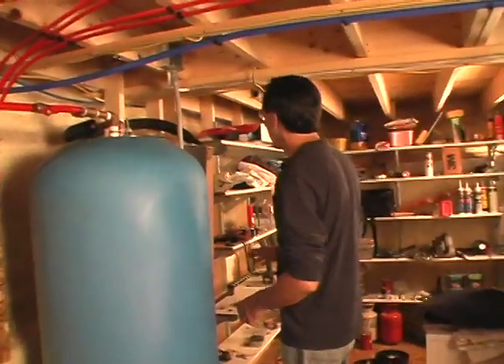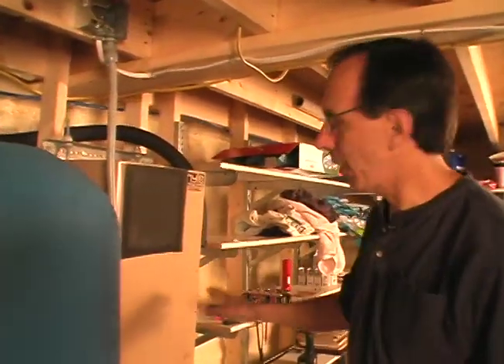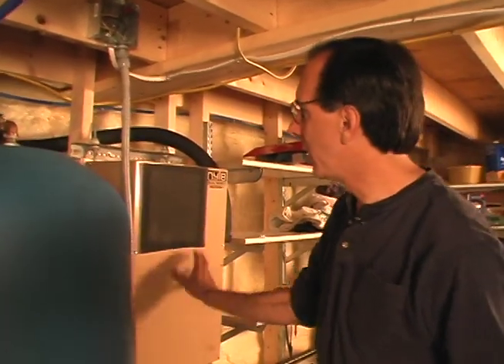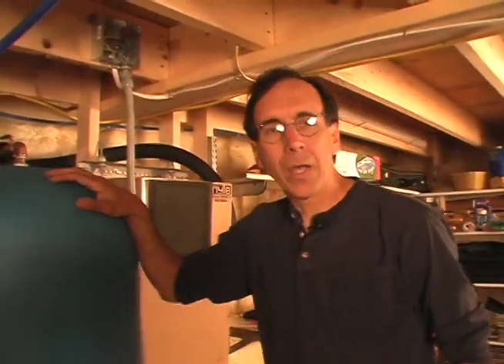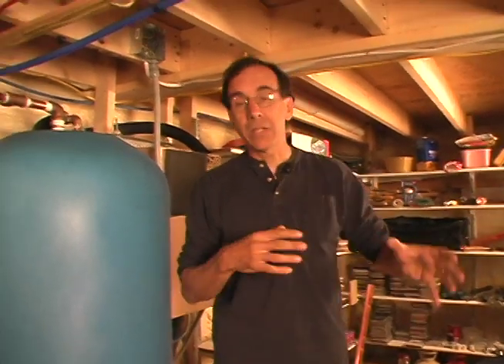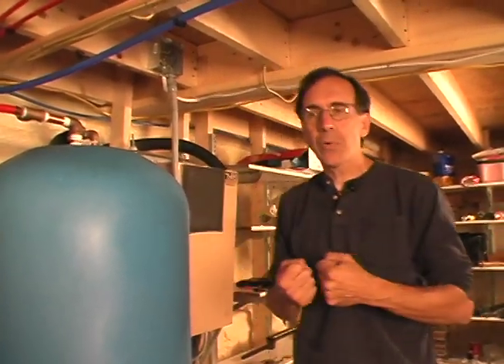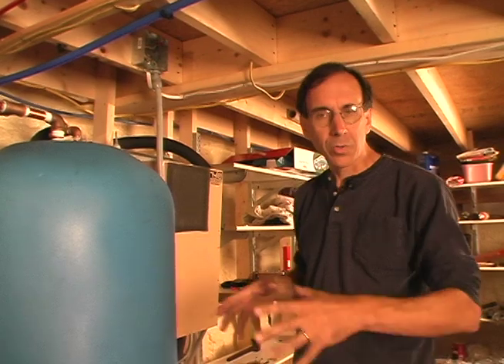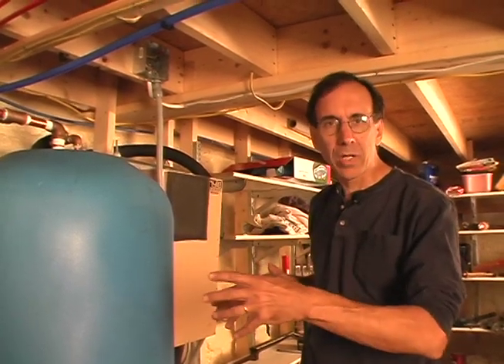We've got a Nyle Corporation heat pump water heater. This is the actual water heater right here. It's hanging on the wall, and what it's doing is making hot water in the basement. It's taking basement air, cooling it down, dehumidifying it, and in the process of extracting heat as it cools down the basement air, it makes domestic hot water, which would normally tie into your electric water heater tank.